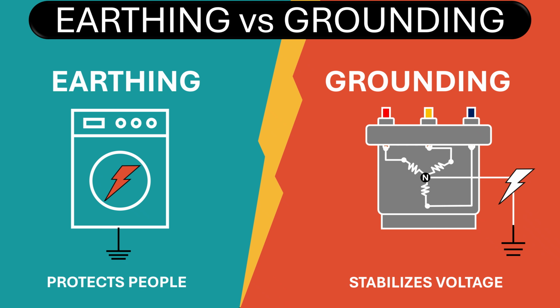Earthing versus grounding, what's the difference? In low voltage and high voltage power systems, the terms earthing and grounding are often confused. But in engineering practice, these two functions influence fault current magnitude, transient behavior, protection coordination, arc flash energy, and system stability. Electrical safety starts with understanding these two concepts. Knowing the basics helps everyone stay safe.